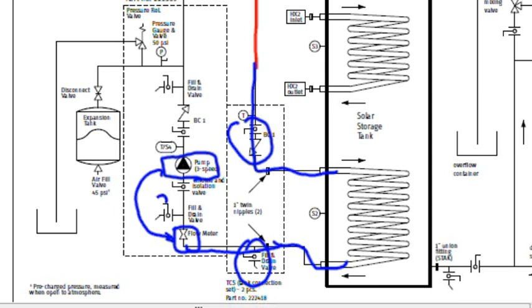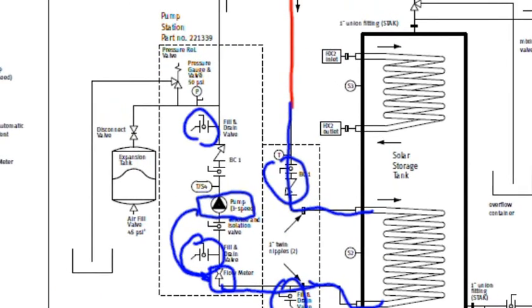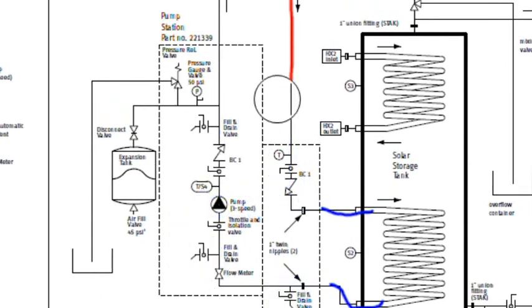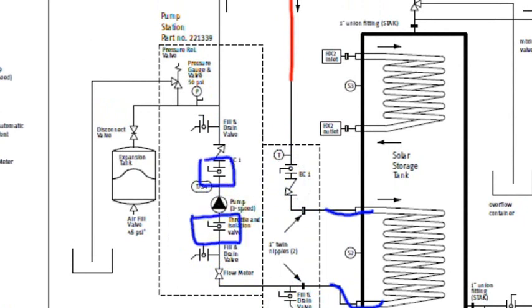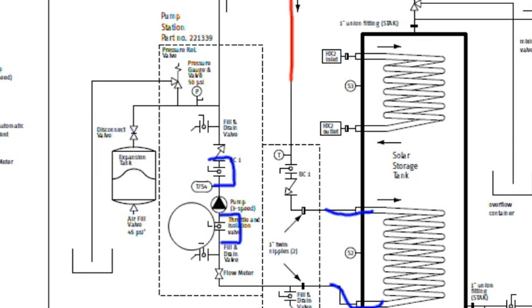Again, another fill and drain valve right there, another fill and drain valve right here. I can turn these valves on or off. I'm going to erase all this right here, but this will allow me to cut out the pump in the system. And I can fill here and here if I had a pump that goes bad. I can also use that to help refill when it comes time to replacing that expansion tank right there.